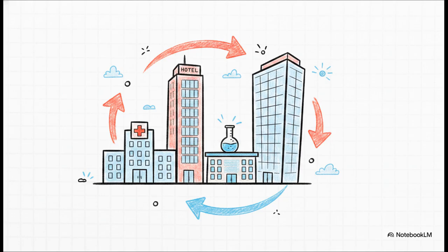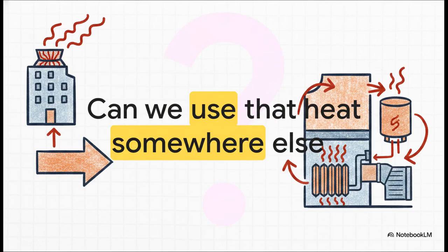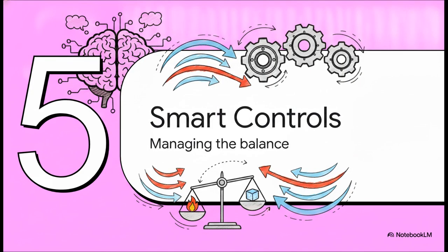We're talking about sprawling hospitals, university campuses, intense laboratories, busy hotels, large high-rise buildings, and central plants that have year-round interior cooling loads. What do they all have in common? They inherently and constantly demand simultaneous cooling and heating. They are always pulling heat out of one zone while desperately injecting heat into another. And this naturally frames the ultimate question that smart building designers and engineers are finally asking themselves. Instead of just automatically throwing heat away outdoors through a cooling tower like we've always done, can we use that heat somewhere else inside the building? Which perfectly tees up Section 5, Smart Controls and Priorities.